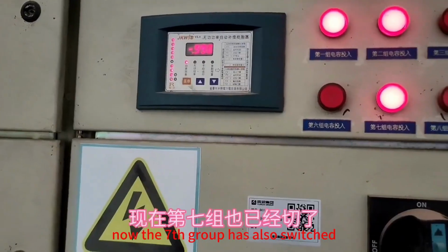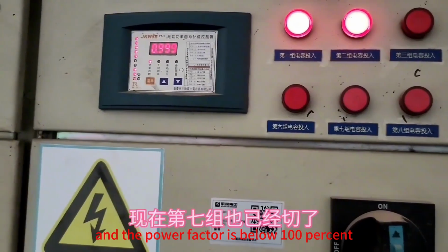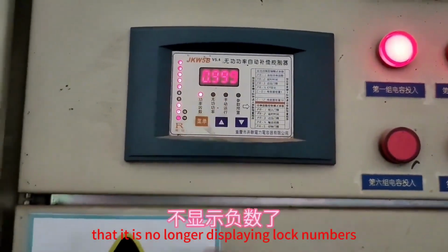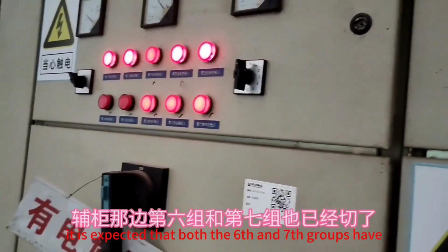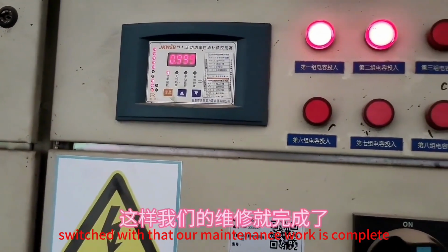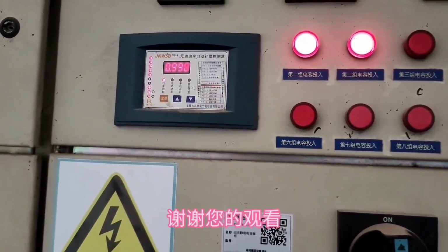Now the 7th group has also switched, and the power factor is below 100%, indicating that it is no longer displaying negative numbers. It is expected that both the 6th and 7th groups have switched. With that, our maintenance work is complete. Thank you for watching.